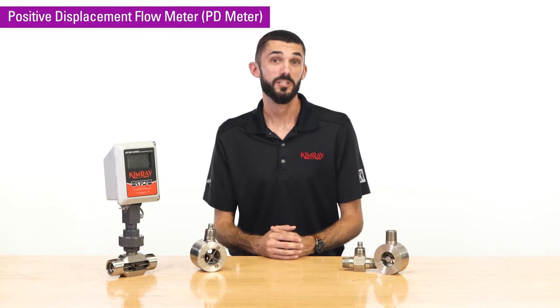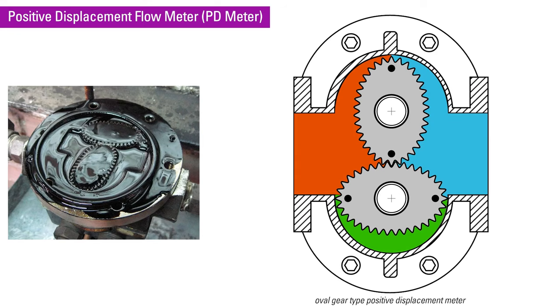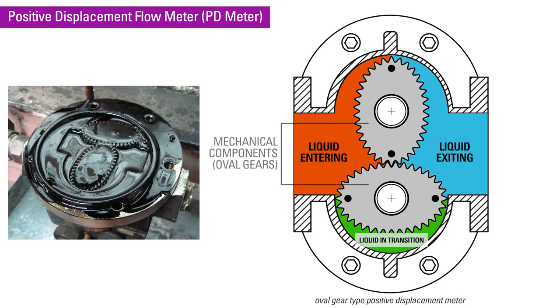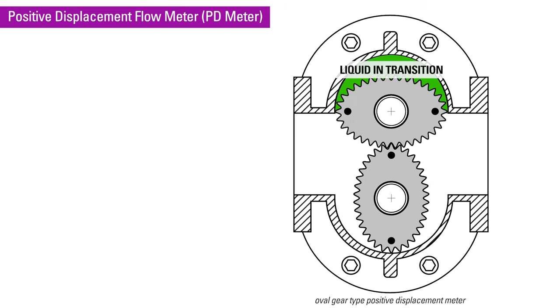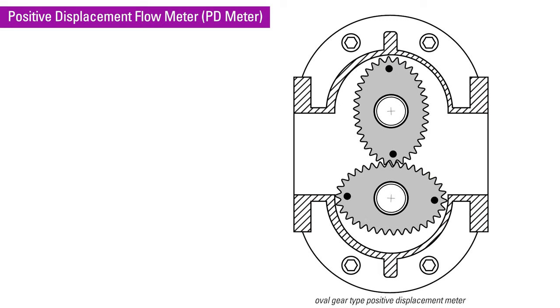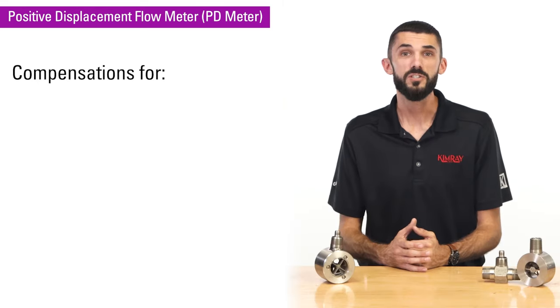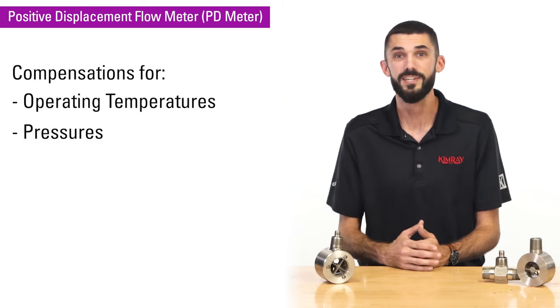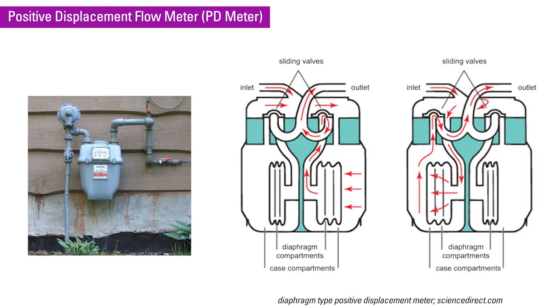The final type of flow meter we're going to talk about is a positive displacement meter. Positive displacement meters use fluid to displace mechanical components to measure volumetric flow. Compensations for operating temperatures and pressures are needed for accurate measurements, just like with all the other meters. The most common type of positive displacement meter is a diaphragm meter, which can be found outside of most houses to meter natural gas usage for utility companies.